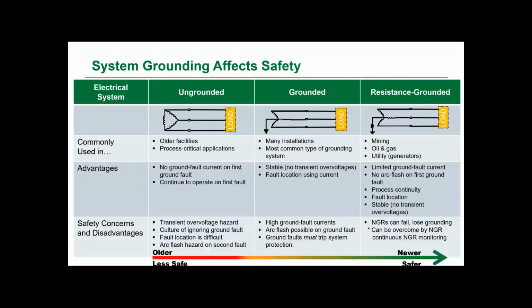Now, one of the more important pieces of electrical safety is system grounding. And this, again, is a lot easier to understand with that up-to-date single line diagram. Starting from the left, ungrounded systems, usually meaning a delta secondary, are mostly found in older facilities, but are still being designed in from time to time for some process industries. Really, this is because of the feature that the first ground fault does not produce any ground fault current. That allows production to continue until there's a convenient time to shut down and find the fault. Now, that advantage does come with a number of significant disadvantages.